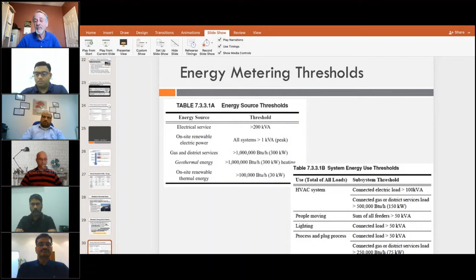So in HVAC, if you have a total connected electrical load of 100 kVA, which is not that large, or lighting systems greater than 50 kVA, again, not that large, and plug loads. So you're basically taking measurements of those 4 main systems. As a minimum, it's only 4 pieces of data you're collecting, but at least you know where the energy is going. And it might give you some information on, say, the lighting system. Maybe your lighting control system is not shutting off lights in a certain part of the building at night, or late in the morning when people are not there. That measurement will tell you. You'll be able to see that from your data and work from that point.